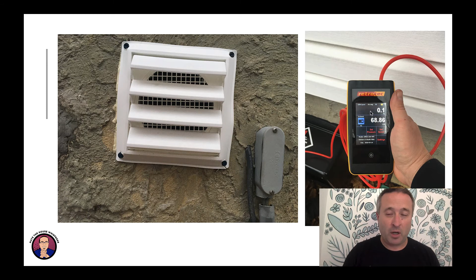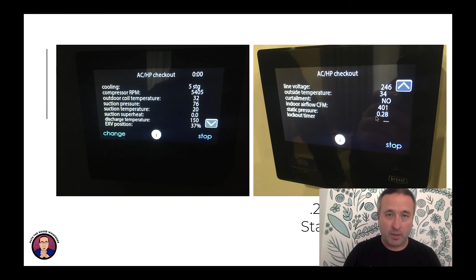Speaking of static pressure, it's fun to be able to measure these. So if you use ICP, Carrier, Bryant equipment, or any of the other ICP brands, if you use the top of the line stat, it will tell you static, and it's not dead on, but it's close enough. So here we are. This unit's running at 5th stage, so flat out. There's your EXV, and we are getting 0.28 inches of external static pressure.